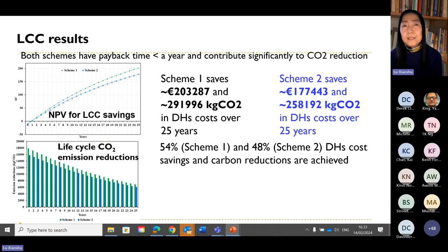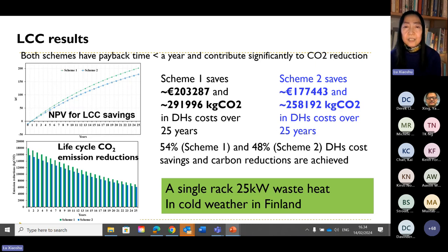Both schemes have a payback time of less than 1 year and contribute significantly to carbon reduction. Scheme one saves over 200,000 euros in energy cost and nearly 300,000 kilos of CO2 in district heating over 25 years. The corresponding values are a bit lower in scheme two. Nevertheless, both solutions achieve very good results, with 54% for scheme one and 48% for scheme two compared with the base case. Also, I would like to remind you that these are observed based on a very small single rack, only 25 kilowatts of waste heat, and in the cold weather in Finland.